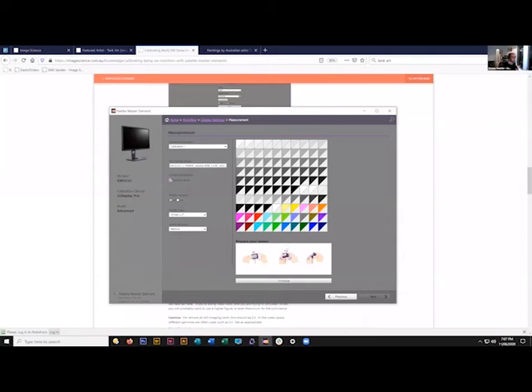One of the questions that always comes up at this point is, does it matter what your ambient light is doing? Do I need to calibrate at night if I work at night? Do I need to calibrate separately for night and day? In general, you certainly don't need to repeat the calibration at different times of day, because the calibrator has a little foam baffle surrounding the lens, so no ambient light is getting in there anyway. It is only reading the output of the monitor. So you can do it at any time of day that suits you.